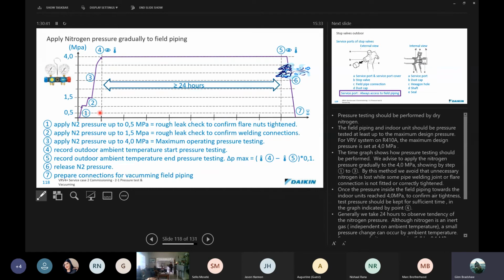It's a rough check. Make sure flare nuts are tightened and all the joints have been welded. It does come across sometimes when you're doing installation that you forget to weld a joint, and it'll pop open. At least you haven't lost a whole lot of nitrogen and caused a massive pressure explosion, as you would if you went straight to 4 megapascals. Then you take it to 1.5 megapascals, another rough check on each of these. You should be walking around the system, listening for leaks, going over joints.